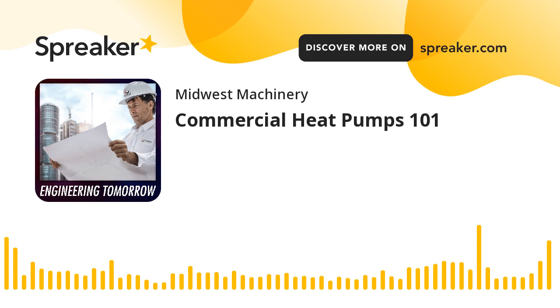Going back to heat pumps, tell me about the different piping configurations and options we can go with. So, when you have water source heat pumps, the typical way that it's installed is two pipes, a supply and return going through your whole building. So you've got two pipes, and actually three if you have a condensate drain that needs to go. Many times that's just taken care of right at the unit, but you run two pipes throughout your whole building. So a supply line going out to the heat pumps, usually around 87, 88 degree water going to the heat pumps, and then the return line coming back to the mechanical room, usually around 97, 98 degrees. So that's the typical layout.